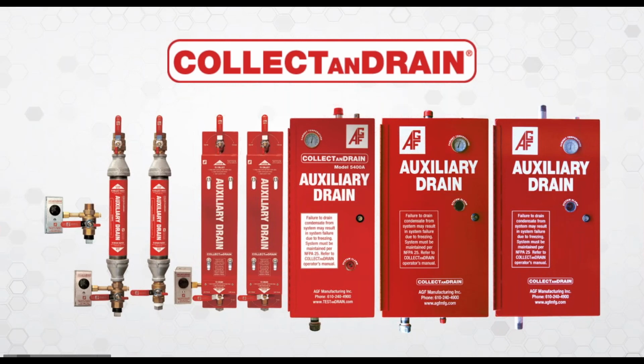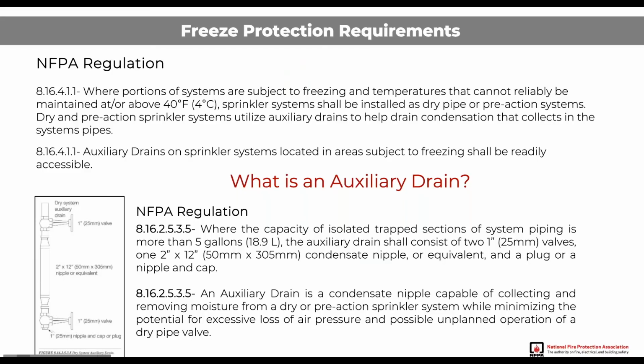And the majority of fire sprinklers are wet sprinkler systems, which means they're full of water. And guys, I'm from Philadelphia, so I'm going to say the word water. Sorry, water, for the Midwest and the rest of the country. But in some systems where you can't have a system full of water, you have it full of compressed air or nitrogen. These are called dry or pre-action systems. And why you have to put those in: code requires that if you can't maintain reliability of 40 degrees or greater in that building, you have to put in a dry pipe system.